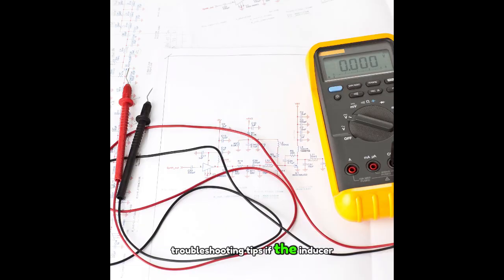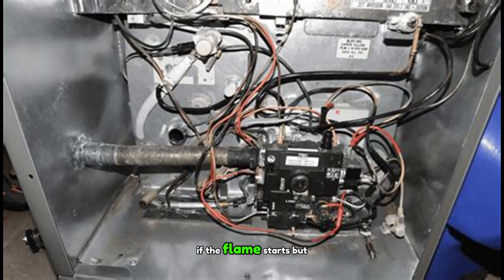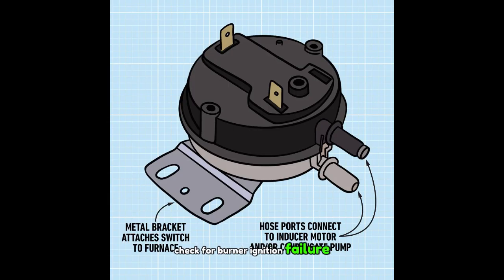Troubleshooting tips. If the inducer runs but no ignition, check the pressure switch or igniter. If the flame starts but shuts off in a few seconds, check the flame sensor. If the blower runs with no heat, check for burner ignition failure or a tripped limit switch. Always test voltage at each stage and follow the sequence with your multimeter and clamp meter.